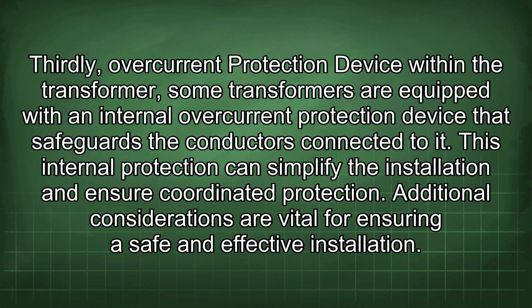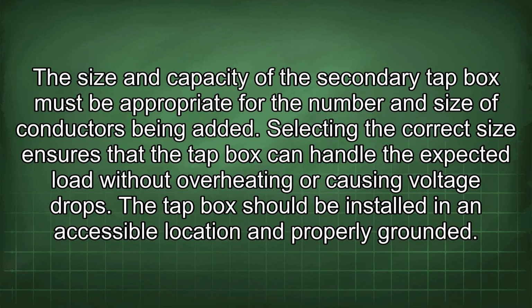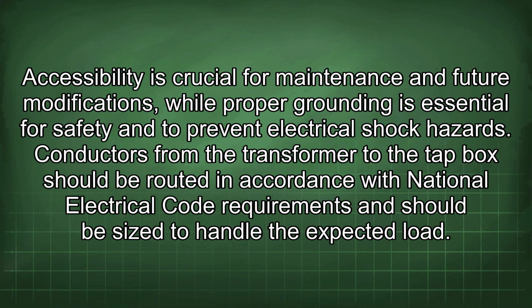Additional considerations are vital for ensuring a safe and effective installation. The size and capacity of the secondary tap box must be appropriate for the number and size of conductors being added. Selecting the correct size ensures that the tap box can handle the expected load without overheating or causing voltage drops. The tap box should be installed in an accessible location and properly grounded. Accessibility is crucial for maintenance and future modifications, while proper grounding is essential for safety and to prevent electrical shock hazards.